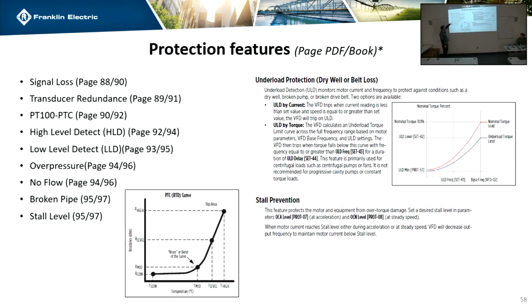No flow, you can have an input set up. Basically, you just put flow as one of the inputs, and you can have a flow sensor come back to the drive, set up a delay just like we do the damper, so the drive's looking for proof of flow. You can also do that in HVAC. You can do that with airflow. So if you're looking for like duct flow and you want proof of flow, you can run it back to the drive.